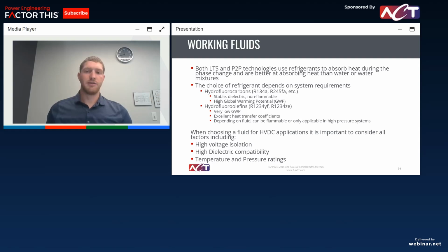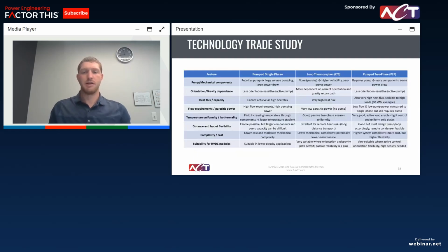So looking at HVDC, the dielectric is probably the biggest thing you're looking at, for that high voltage isolation, and you want to make sure you're considering temperature and pressure ratings. And if global warming potential is a factor in that choice, it's important to consider as well. So looking at just an overview, I won't go all the way into all of these. This kind of summarizes some of the stuff I talked about.